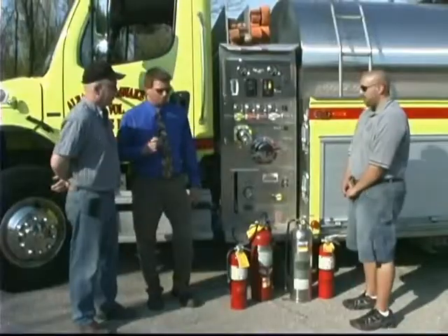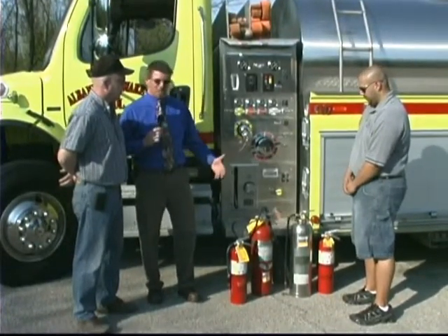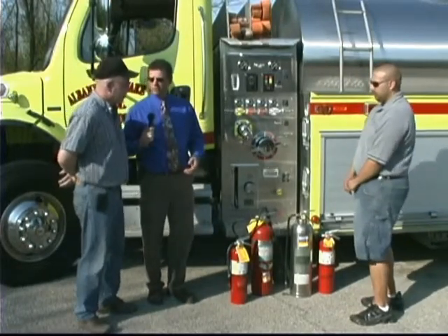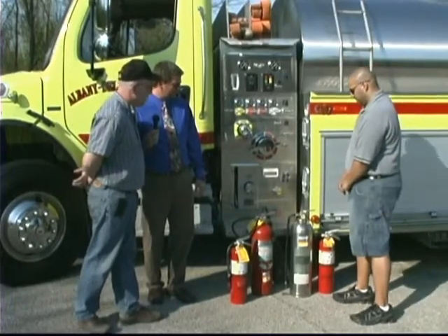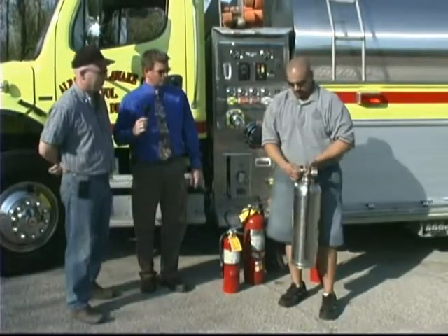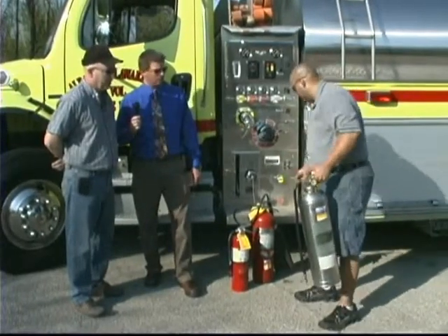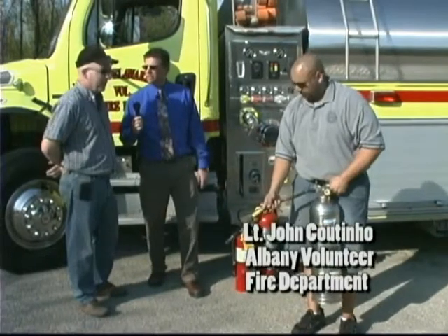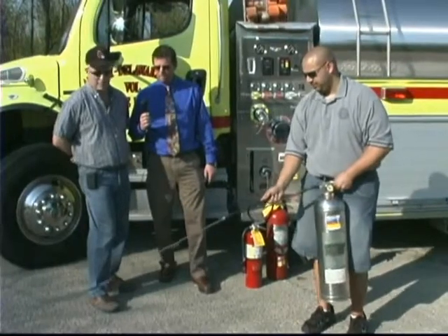Okay. All right. So I understand all these fire extinguishers appear to be the same type of mechanism on top. Is there a common way to use all these fire extinguishers? Yes, there is, Jason. It is used by a common acronym, PASS. It means pull, which you pull the pin, then you aim, squeeze the trigger, and sweep. So Lieutenant Coutinho here is going to demonstrate that for us. So you're just pulling the pin. Is that fairly easy to do? That's correct. And then how much pressure does it take to actually compress that valve at the top? Very little. Aim, squeeze, and sweep.